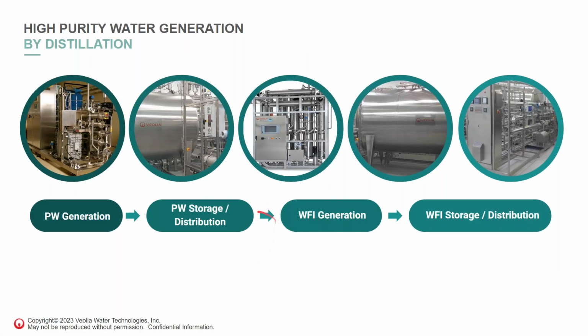So just to give you a pictorial representation of that type of system, to produce WFI water, you would look at having some sort of generation system, possibly a storage system that feeds into the WFI unit, and then the WFI unit produces WFI water for the WFI tank, and then the distribution loop. Those would be probably the 5 stages you're looking at. Sometimes the purified water system, if the customer just has a WFI side, could feed the still directly, so you don't need this part of the system. But for the moment, let's just consider the system as we see it there as part of this presentation as we go forward.